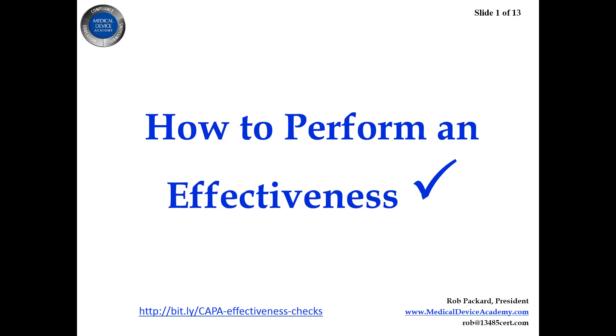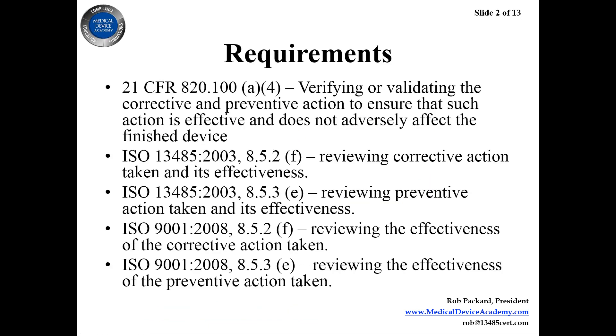At the bottom of this slide there's a link to an article I wrote on how to do CAPA effectiveness checks. Here are all the requirements in the regulations for CAPA effectiveness checks. In 21 CFR 820.100 — the subsection of the QSR specific to corrective and preventive action — sub-subsection A4 says: verifying or validating the corrective and preventive actions to ensure that such action is effective and does not adversely affect the finished device. The first two additional references are for ISO 13485 corrective and preventive actions, and then ISO 9001. In all three regulations you have the requirement for performing an effectiveness check.